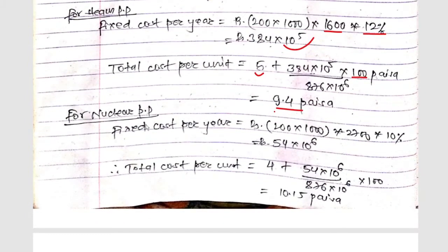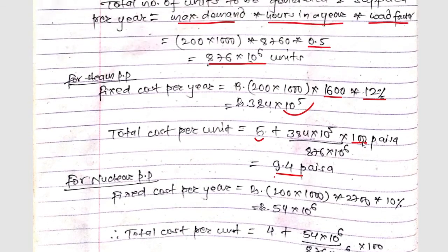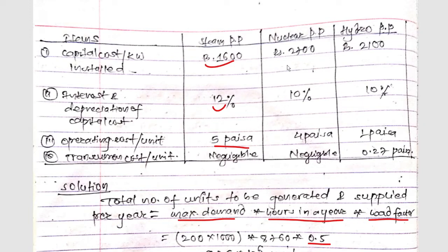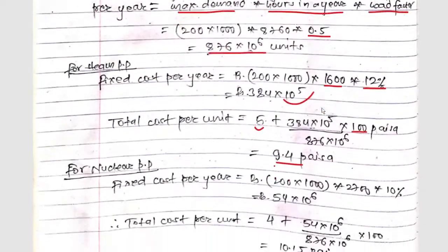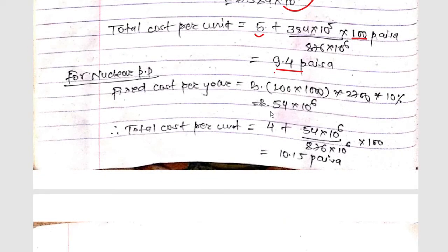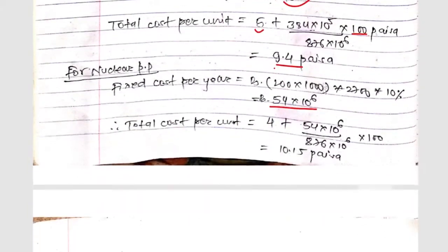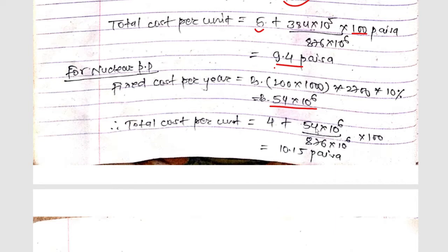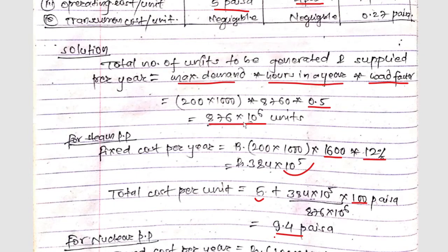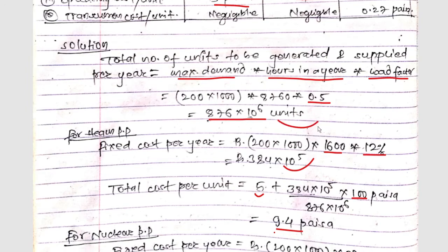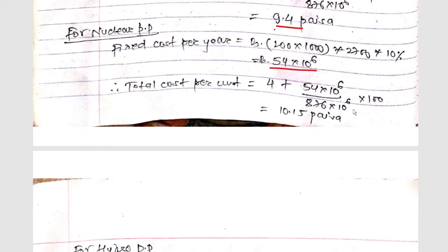For the nuclear power plant, the fixed cost per year is: 200×1000 kW × capital cost of 2700 rupees/kW × interest and depreciation of 10% = 54×10⁶ rupees. The total cost per unit is operating cost of 4 paisa plus fixed cost converted to paisa: (54×10⁶ × 100) / (876×10⁶) = 10.15 paisa per unit.